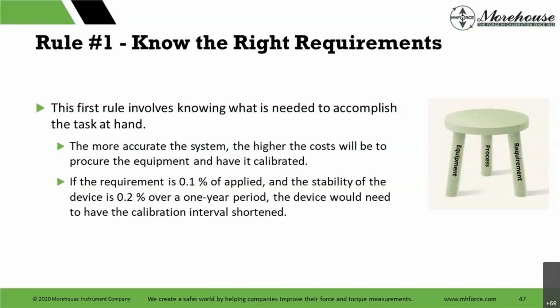I said the $50,000 meter, that's the high-end meter. The next meter down that I recommend is about $2,800. So, pretty sharp decline. Again, that $2,800 meter may be really, really good for what you need to do. So know the rules, know the requirements. If the requirement is 0.1% of applied force and the stability of the device is 0.2% over a 1-year period, the device would need to have the calibration interval shortened.